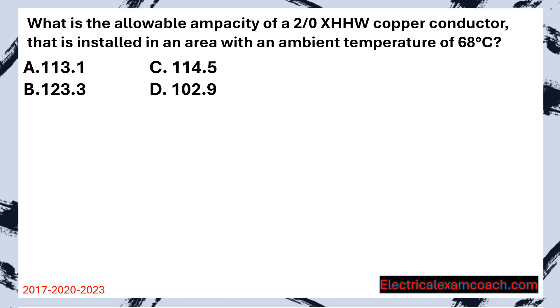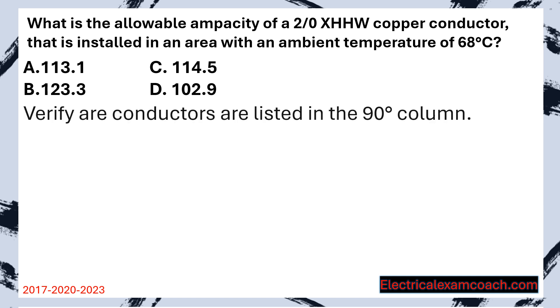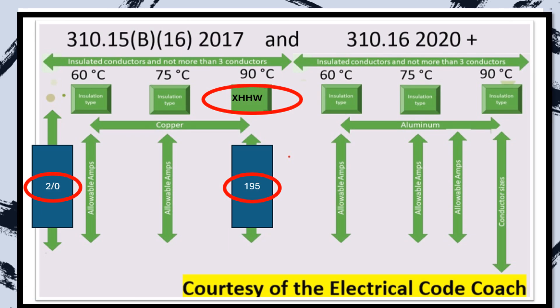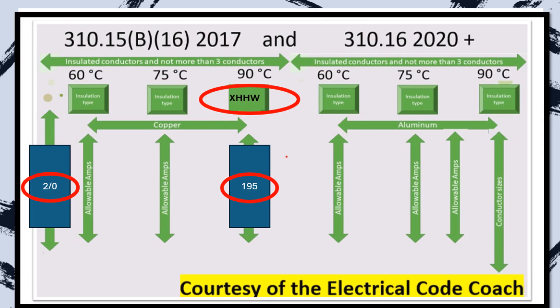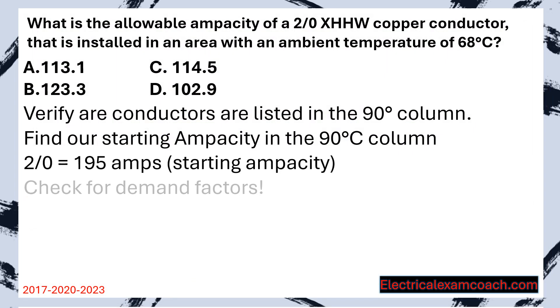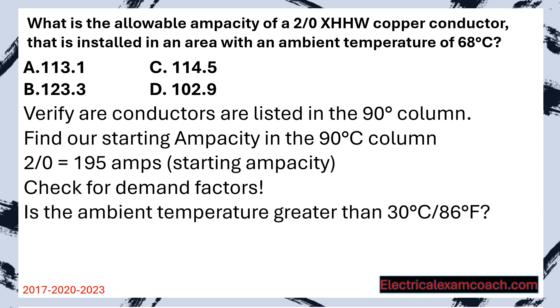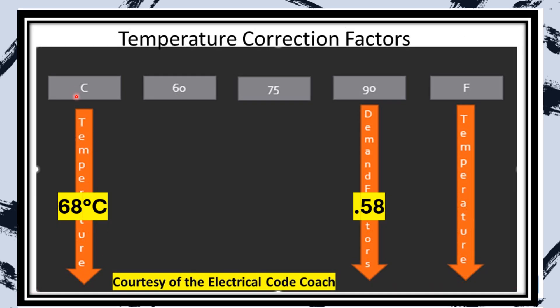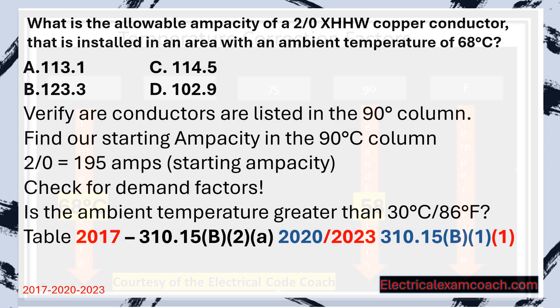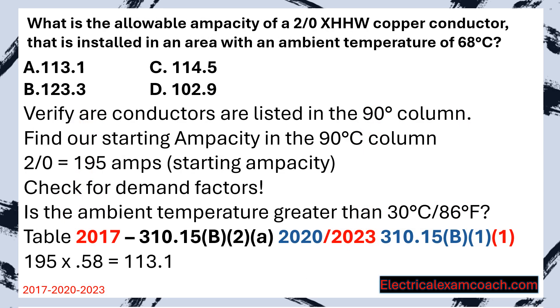Final problem: What is the allowable ampacity of a 2-aught XHHW copper conductor installed in an area with an ambient temperature of 68 degrees Celsius? Step 1, verify XHHW is in the 90 degrees C column — it's there. Find the starting ampacity: 2-aught copper crosses over to 195 amps. Check for demand factors — ambient temperature is greater than 30 degrees Celsius, so there is one. Head to the corrections table, start on the left-hand side because it's Celsius, cross over to the 90 degrees C column, and find a correction factor of 0.58. Multiply 195 by 0.58 for a new allowable ampacity of 113.1 amps. Select A.